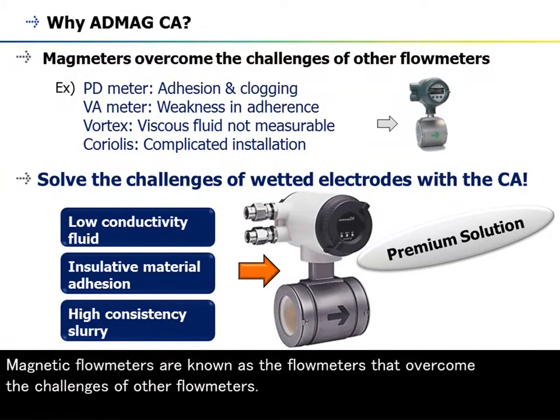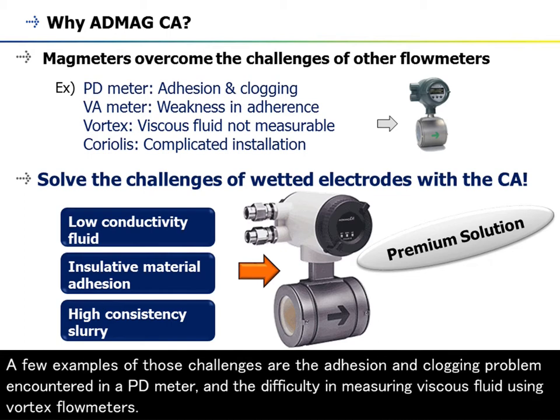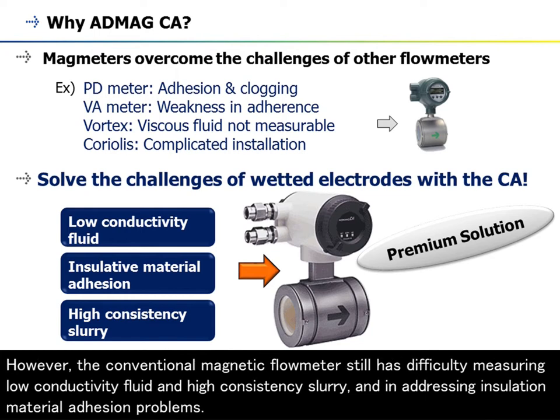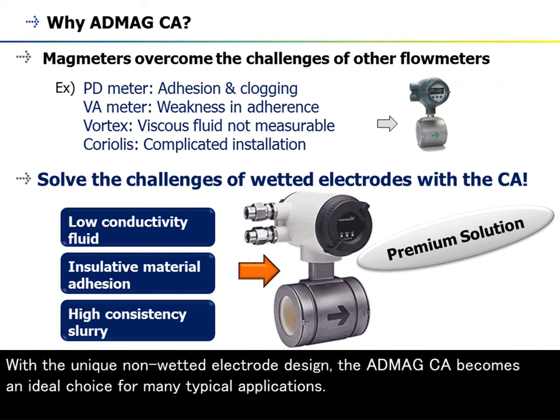Magnetic flow meters are known as the flow meters that overcome the challenges of other flow meters. A few examples of those challenges are the adhesion and clogging problem encountered in a PD meter, and the difficulty in measuring viscous fluid using vortex flow meters. However, the conventional magnetic flow meter still has difficulty measuring low-conductivity fluid and high-consistency slurry, and in addressing insulation material adhesion problems. With the unique non-wetted electrode design, the ADMAG CA becomes an ideal choice for many typical applications.